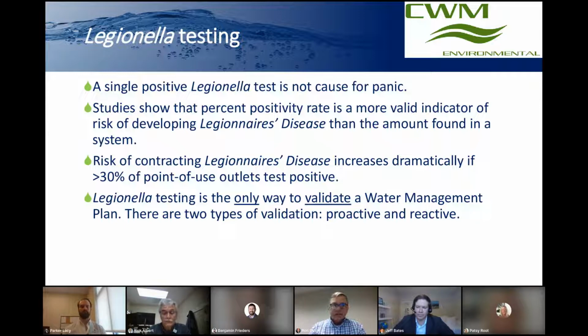One of the recent pushes is: is your sample size large enough? I know because of budget constraints, there are a lot of facilities apprehensive about loading up on tests, so they might only do one to three per session. I understand that from a budget perspective, but from an overall standpoint, is your sample size large enough? These are all suggestions, not requirements, only recommendations, and we suggest you do at least a minimum of 10 samples per building.